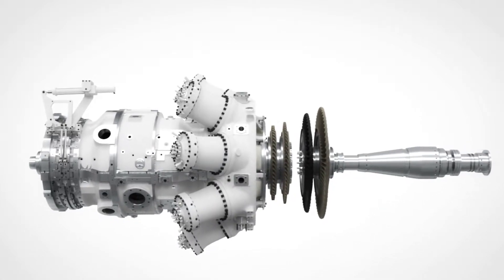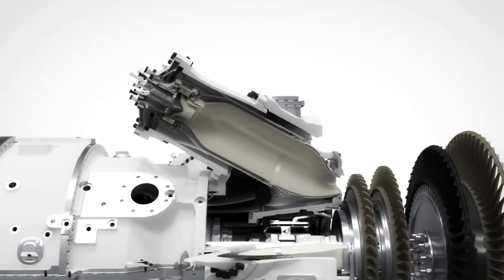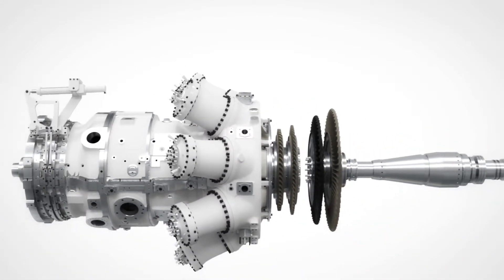The new combustor features the fourth generation of DLE burners from Siemens. The burners are designed to further increase the power turndown range compared to its predecessors, maintaining NOx and CO emissions well within legislation levels. The DLE turndown capability enables the use of large, single turbines replacing multiple small units, allowing the same operating envelope. It offers robust and stable operation with dual fuel online switchover capabilities.